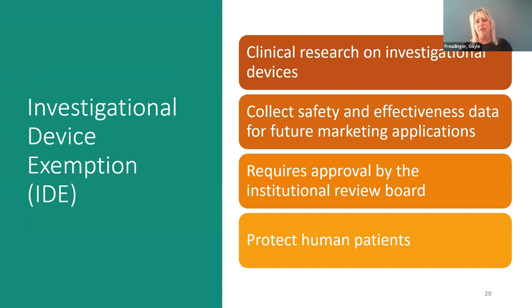The investigational device exemption is a submission that's used when you're not bringing your product to market. So this is kind of a unique situation here. It's really for clinical research or investigational devices. You still will need to collect safety and effectiveness data. And the purpose of the IDE is to protect human patients, which again is the FDA's goal, and it requires approval by the Institutional Review Board. So you're still going to need to collect your safety and effectiveness data there.